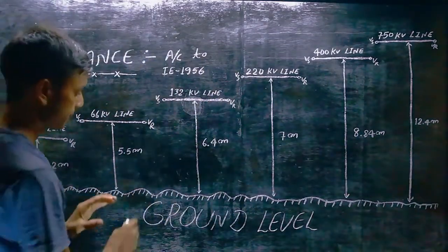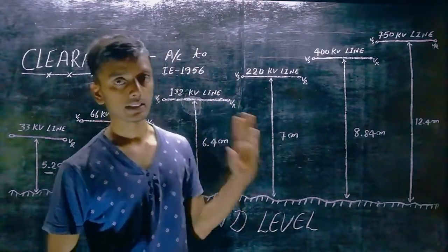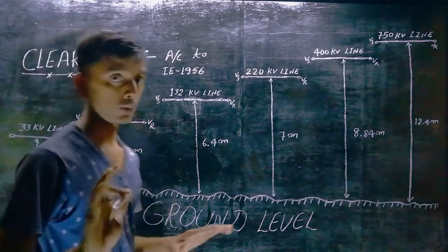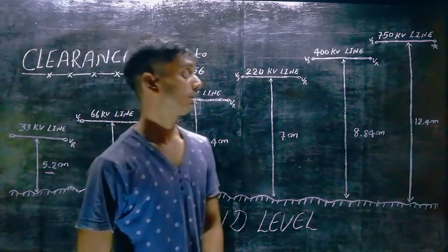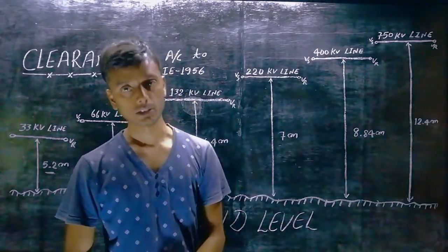As per IE 1956 rules, for 132 kV lines your clearance is 6.4 meters. And you can see that the distance for 400 kV lines is 8.84 meters.